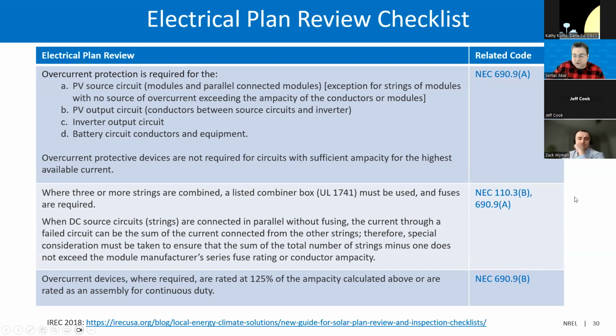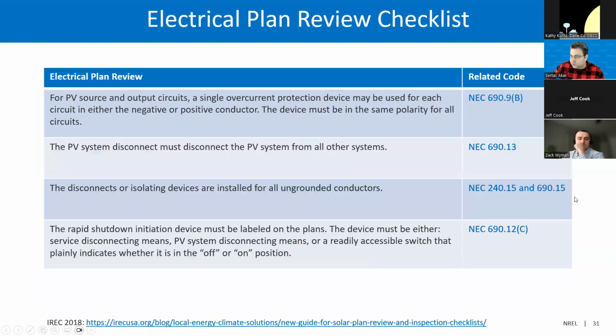110.3(B) covers these codes. There are a couple more codes for the electrical plan, such as for the PV source and output circuit: a single overcurrent protection device may be used for each circuit in either the negative or positive conductor. The device must be in the same polarity for all circuits. And the PV system disconnects must disconnect the PV system from all other systems. And the disconnects or isolating devices are installed for all ungrounded conductors.